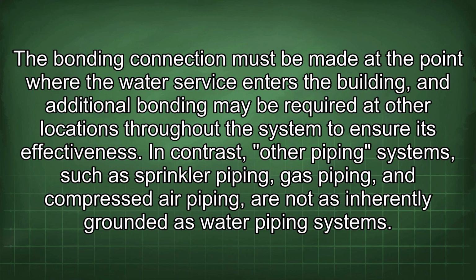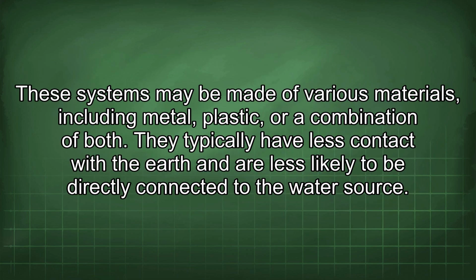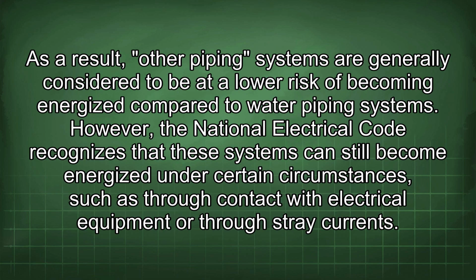In contrast, other piping systems, such as sprinkler piping, gas piping, and compressed air piping, are not as inherently grounded as water piping systems. These systems may be made of various materials, including metal, plastic, or a combination of both. They typically have less contact with the earth and are less likely to be directly connected to the water source. As a result, other piping systems are generally considered to be at a lower risk of becoming energized compared to water piping systems. However, the National Electrical Code recognizes that these systems can still become energized under certain circumstances, such as through contact with electrical equipment or through stray currents.